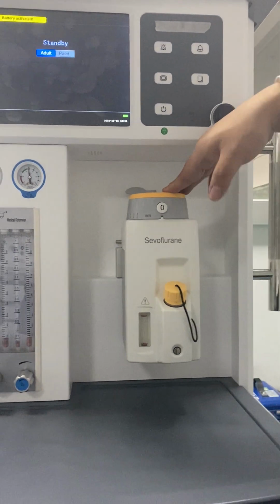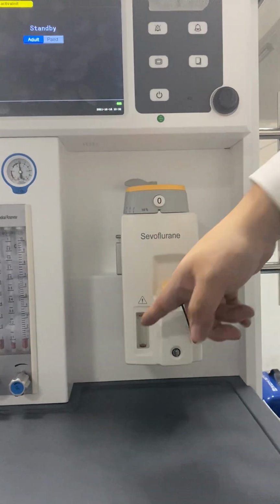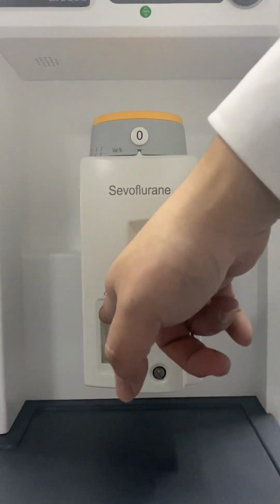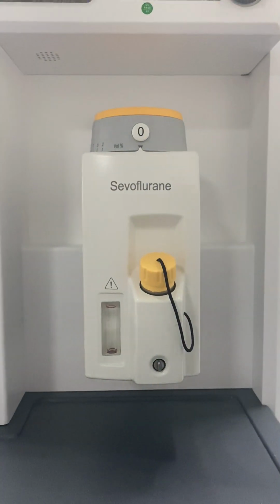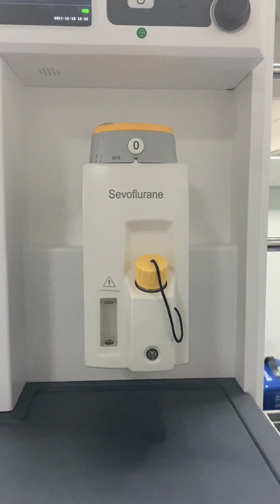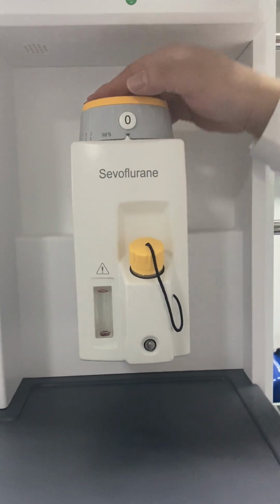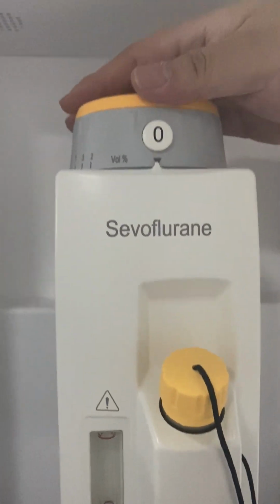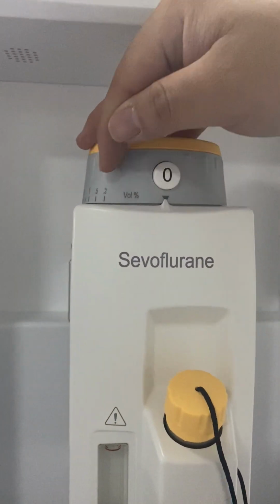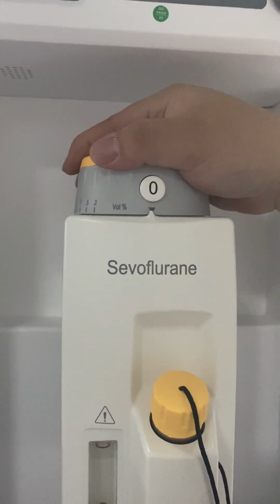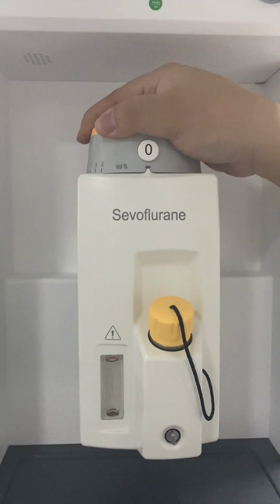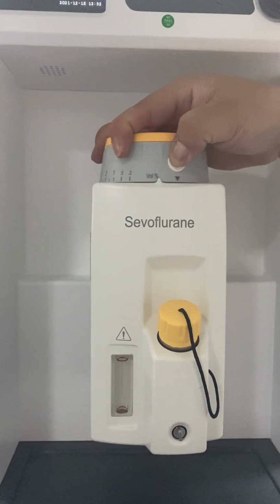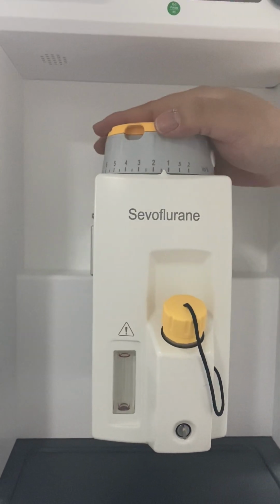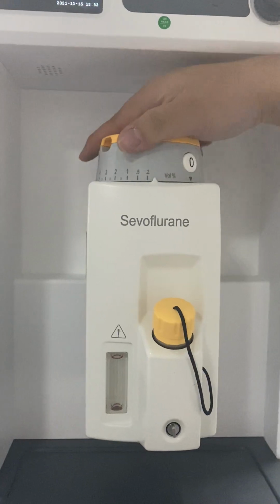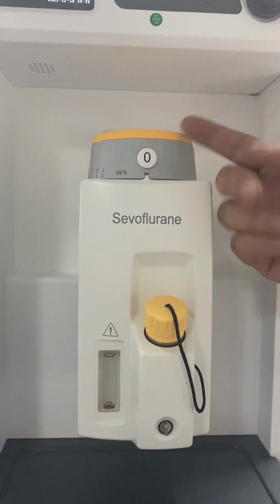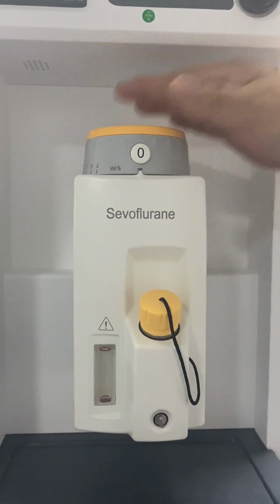Then the vaporizer itself actually has several functions. The first, you can tell the capacity from this window. So you will know if it's already empty or full, or how much medicine is still in the bottle. And also here we have a self-lock function. You can see here it's from 0 to 8%, because this is self-locking. So if I want to adjust it, you can see now it cannot be moved. Only if I press this 0 button can we move it and set the concentration of the anesthetic medicine. And when you change to 0, this button will be pushed out, so then it will be steady. So it's just for safety concerns.